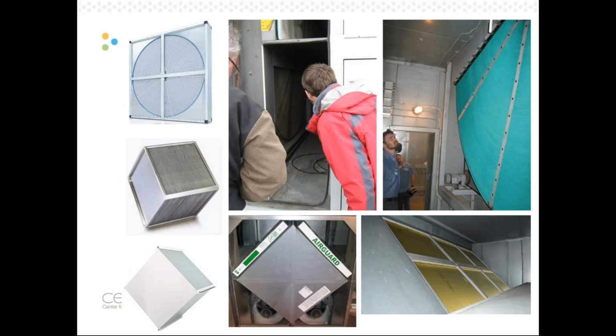This is what ERVs look like in practice. On the left, I have some images from product literature. On the top left, I have a total enthalpy wheel. Under that is a plate heat exchanger. It transfers temperature only. The total enthalpy wheel transfers temperature and moisture. And then the bottom left is a membrane plate heat exchanger, which transfers both temperature and moisture.